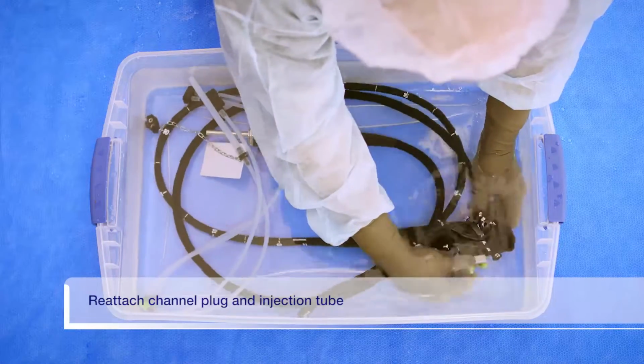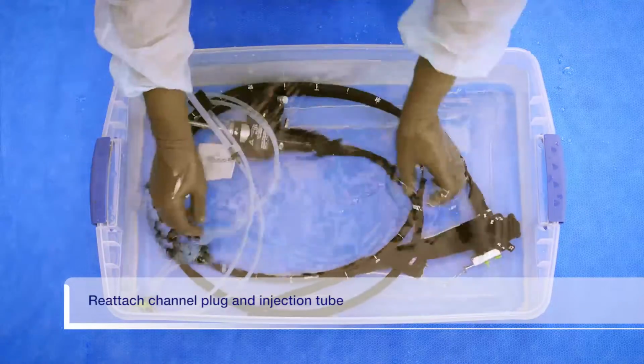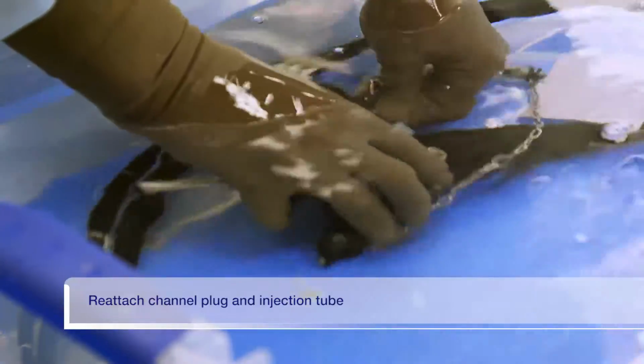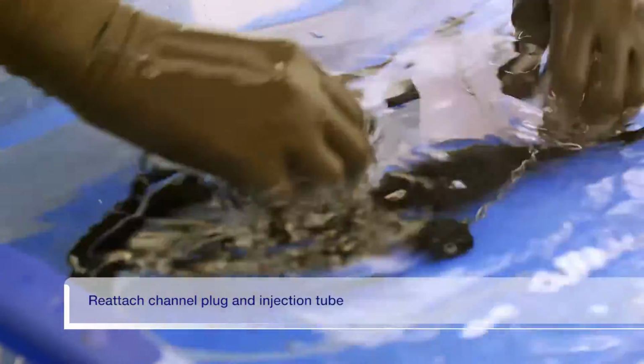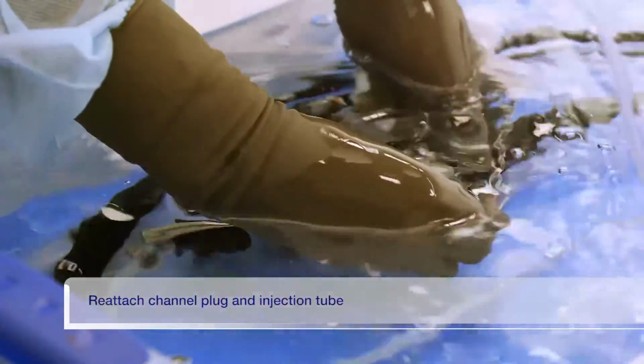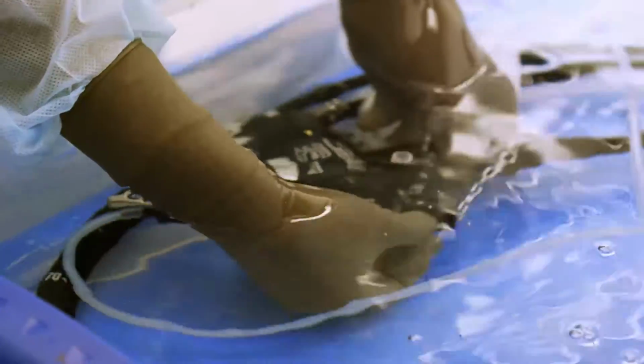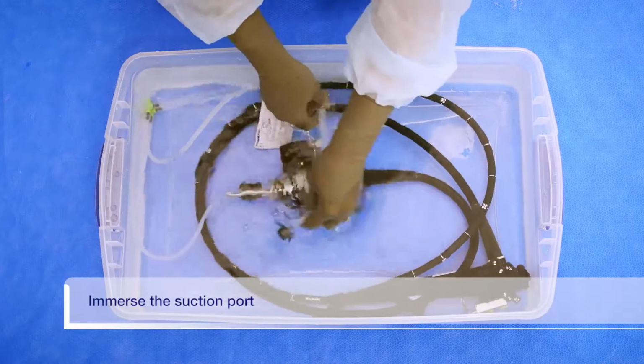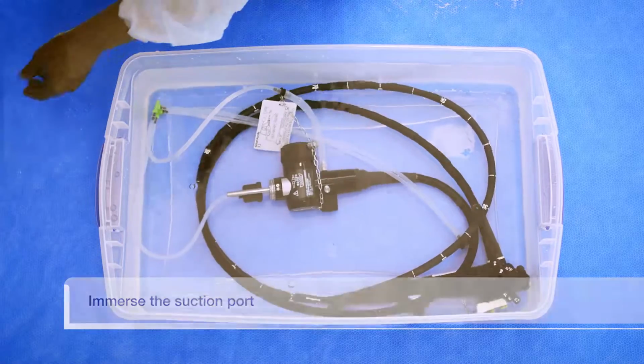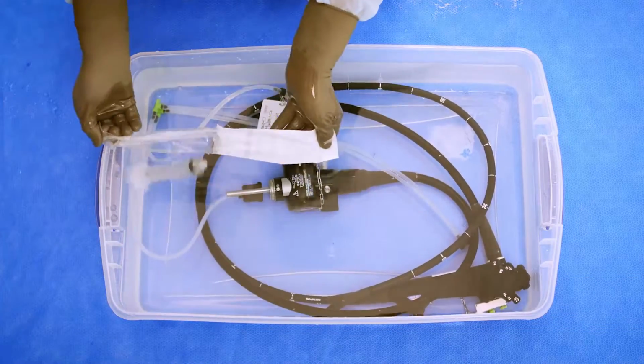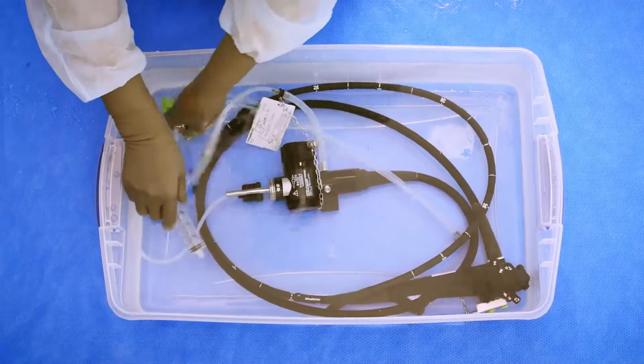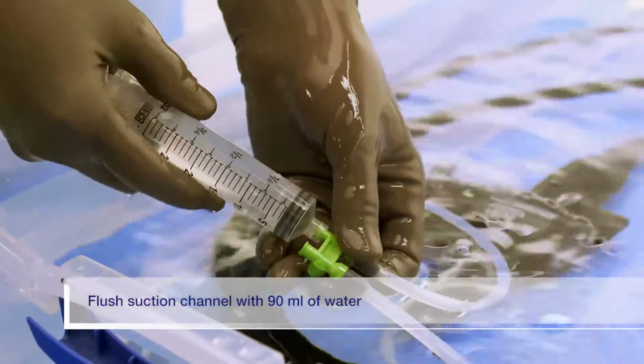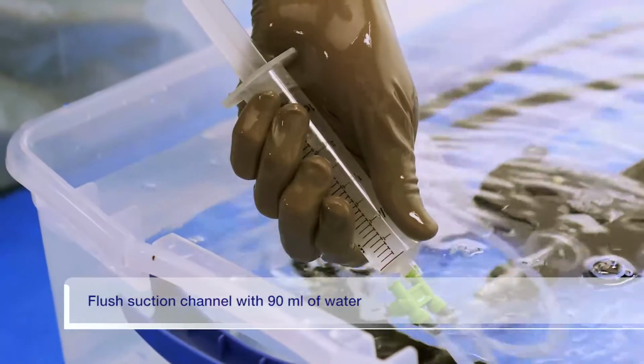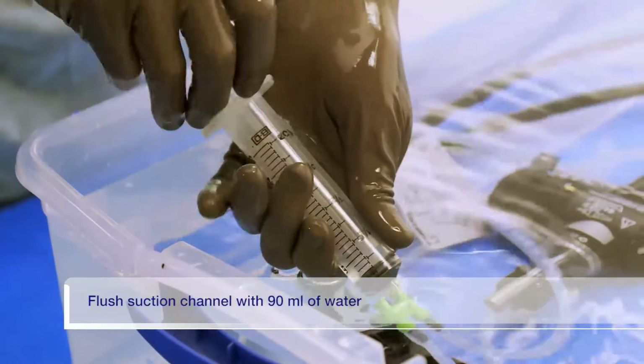Reattach the channel plug and injection tube to the endoscope. Ensure that the suction port of the injection tube is immersed in the rinse water. Attach a sterile 30 milliliter syringe to the suction channel port of the injection tube and flush the suction channel with 90 milliliters of the rinse water, that is, by pumping the syringe at least 3 times.